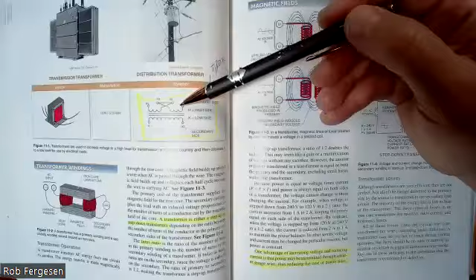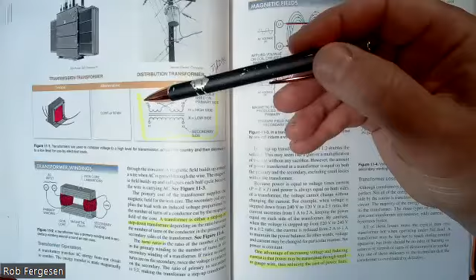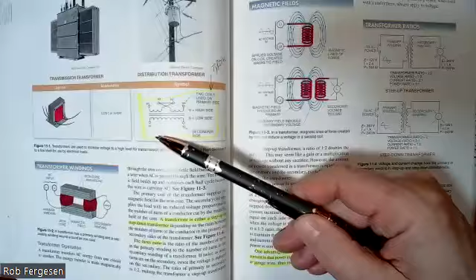So typically on a transformer, you're going to see the primary coil labeled H1, 2, 3, and 4. You can set this up to have a variety of voltage inputs depending on how you put jumpers between H2 and H3, where you attach your power connections. In this case, we're implying they get hooked to H1 and H4. And then on the secondary side, they're using the terms X1 and X2. That is also a typical numbering scheme for the secondary on a power transformer. All right, so these are all very important little symbols that you guys should understand what they mean.